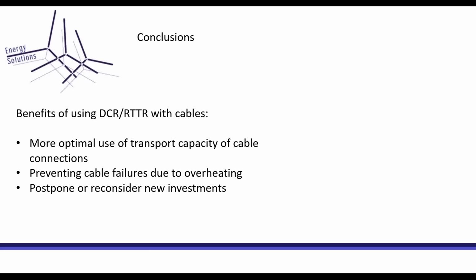So these are just 3 examples of how DCR can be used in underground power cables. You can use the transport capacity in a much better way, because you know the temperature, you know the actual ampacity of the cable, but it can also be used to prevent cable failures.